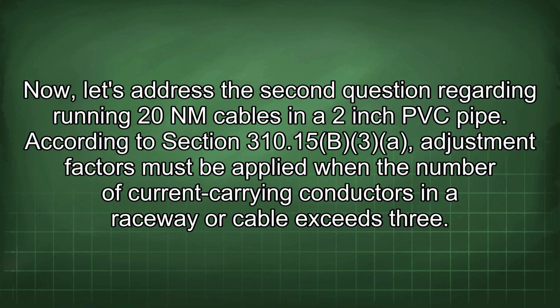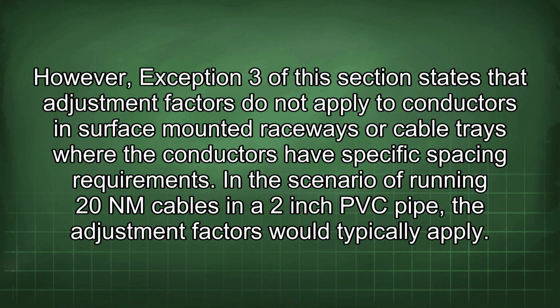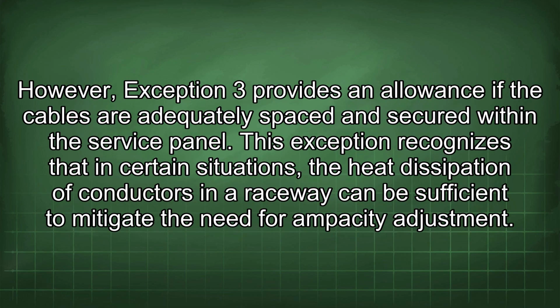Now, let's address the second question regarding running 20 NM cables in a 2-inch PVC pipe. According to Section 310.15(B)(3), adjustment factors must be applied when the number of current-carrying conductors in a raceway or cable exceeds 3. However, Exception 3 of this section states that adjustment factors do not apply to conductors in surface-mounted raceways or cable trays where the conductors have specific spacing requirements. In the scenario of running 20 NM cables in a 2-inch PVC pipe, the adjustment factors would typically apply. However, Exception 3 provides an allowance if the cables are adequately spaced and secured within the service panel.